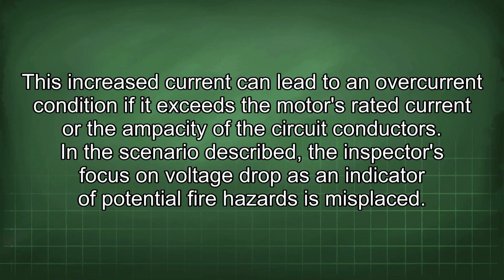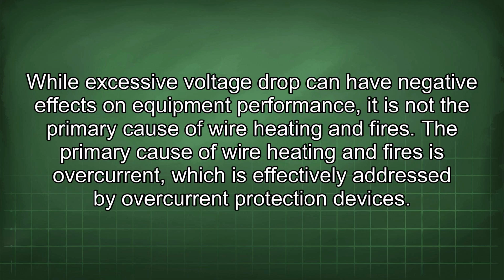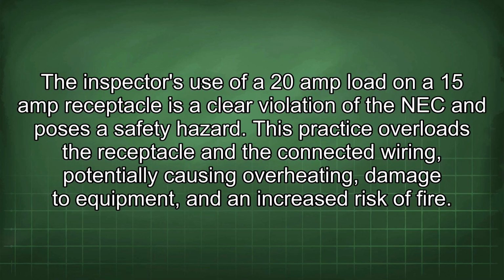While excessive voltage drop can have negative effects on equipment performance, it is not the primary cause of wire heating and fires. The primary cause of wire heating and fires is overcurrent, which is effectively addressed by overcurrent protection devices. The inspector's use of a 20 amp load on a 15 amp receptacle is a clear violation of the NEC and poses a safety hazard. This practice overloads the receptacle and the connected wiring, potentially causing overheating, damage to equipment, and an increased risk of fire.